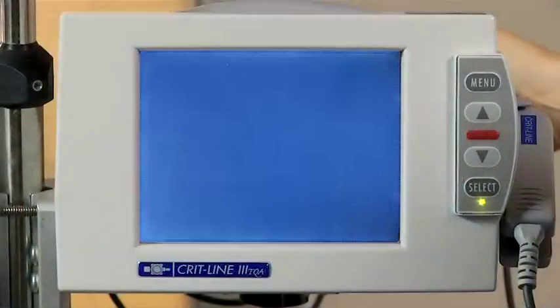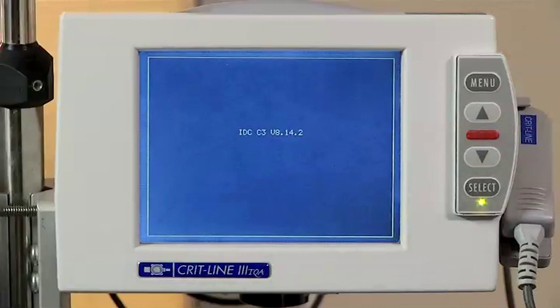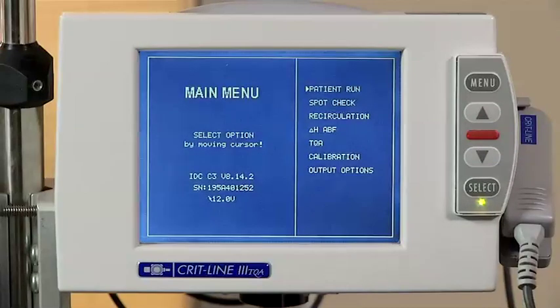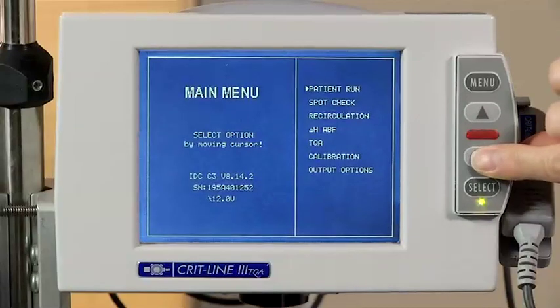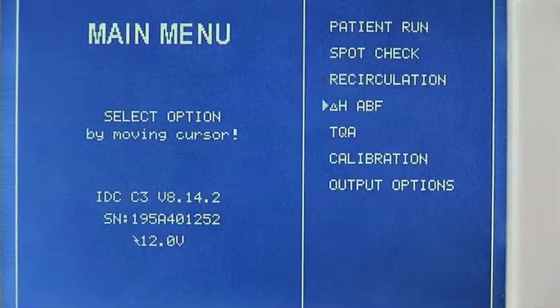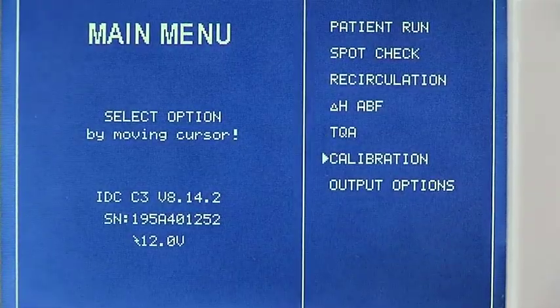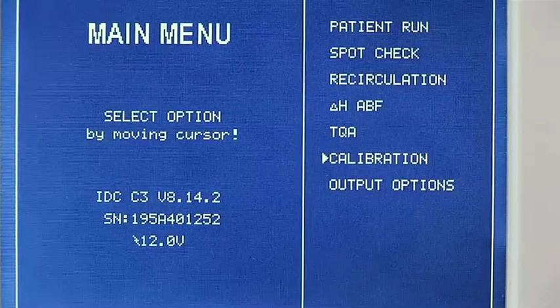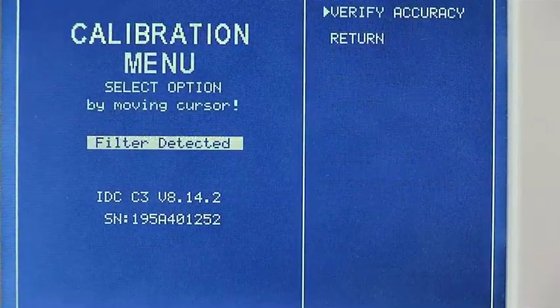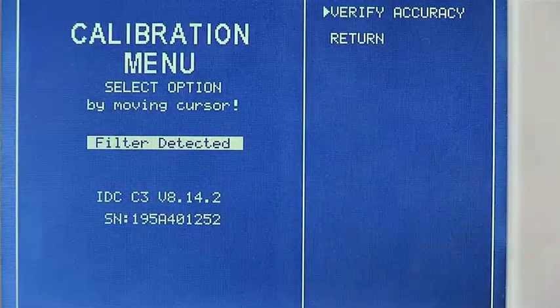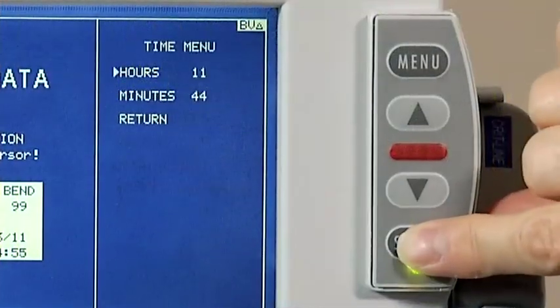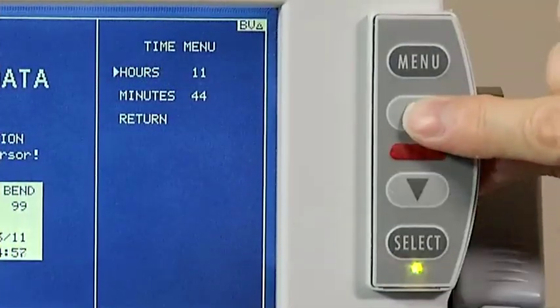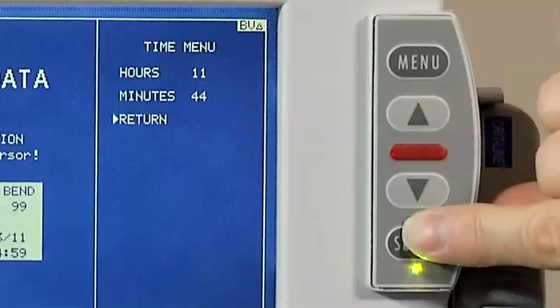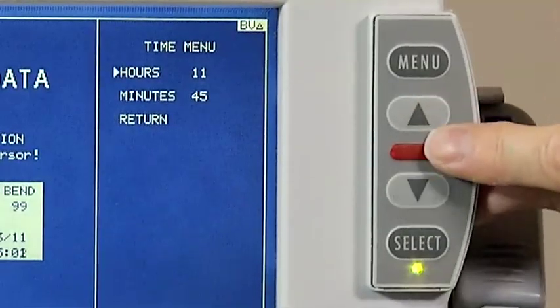When you turn the CritLine monitor on, you will see the main menu unless there is still data in the memory. From the main menu, you will scroll to either Patient Run to begin a patient treatment or Calibration to verify the accuracy of the CritLine monitor. The CritLine monitor is a menu-driven system. To move the cursor, simply press either the up arrow or the down arrow. When the cursor is at the option you want to choose, press the Select button.